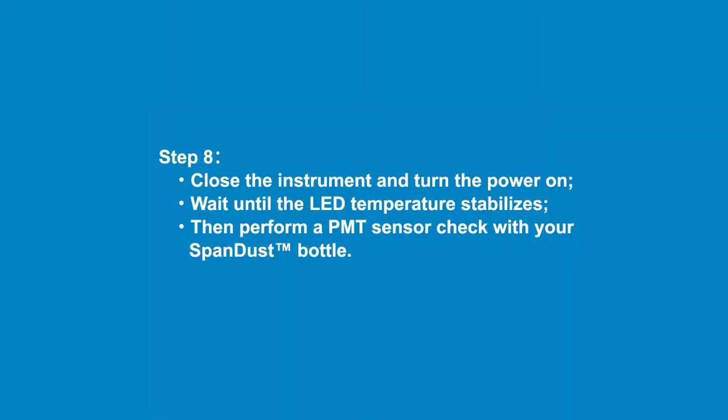Step 8: Close the instrument and turn the power on. Wait until the LED temperature stabilizes, and then perform a PMT sensor check with your SpanDust bottle.